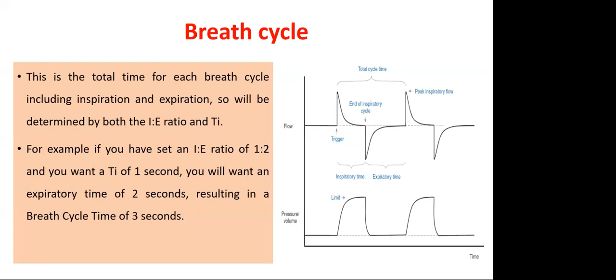So you can see on page 2, here you can see TI, 0.67 seconds. You can see here the rate is set at 30 per minute and the breath cycle is 2 seconds. So your I time depends on that. As I said, each breath cycle is 2 seconds, and out of that your inspiration is 1:2. So 1/3 of your 2 seconds is your inspiration. That is 0.67 seconds, your I time.